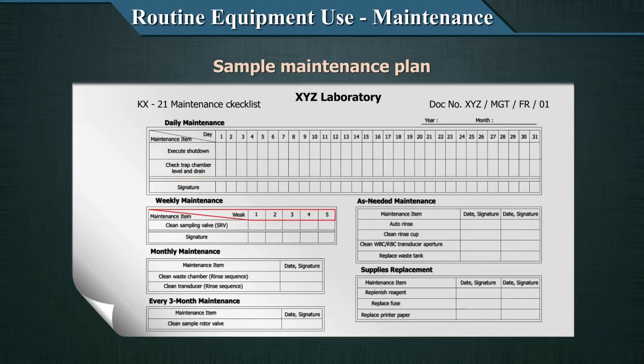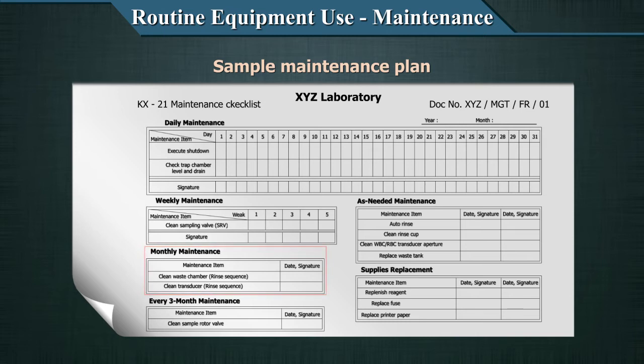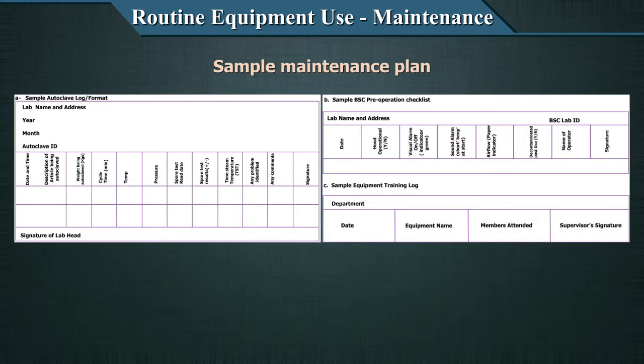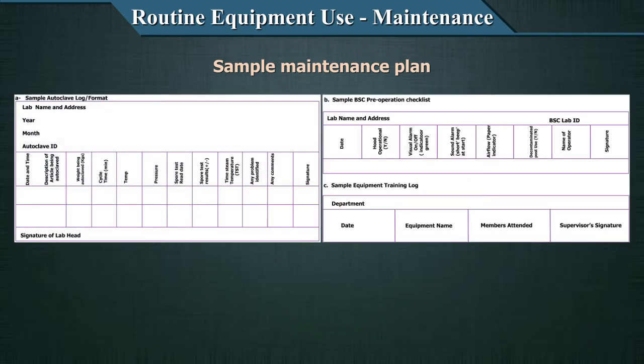For weekly maintenance, there are 4 or 5 weeks in a month. Every Monday, certain tasks are to be done, checked off, and documented. Following that, there will be monthly maintenance schedules. Another example shown is an equipment cleaning and decontamination format, a biosafety cabinet operation format, pre-operational checklist, and sample equipment training log. Training logs are also very important, and every aspect of equipment management has to be logged, formatted, and recorded.